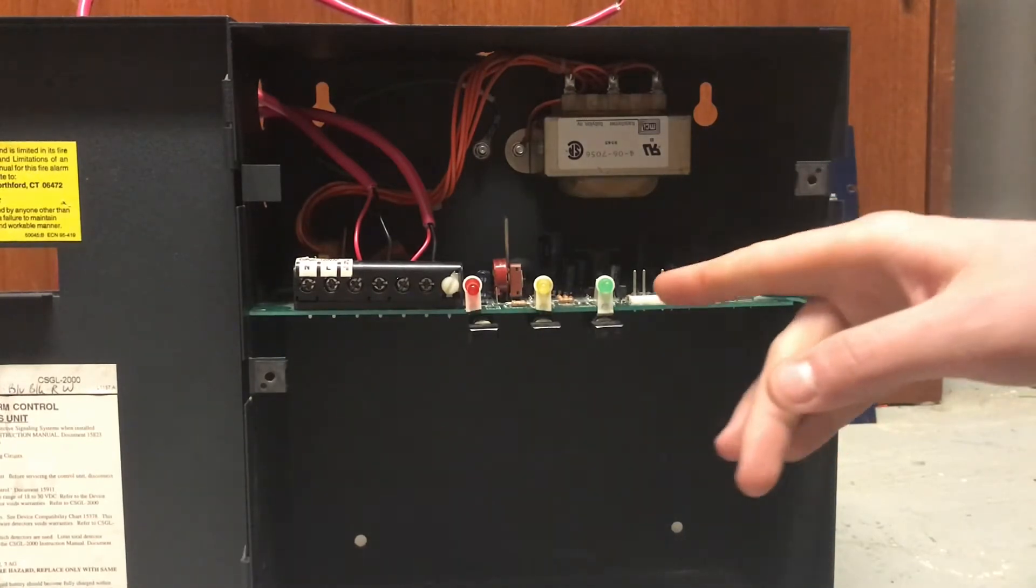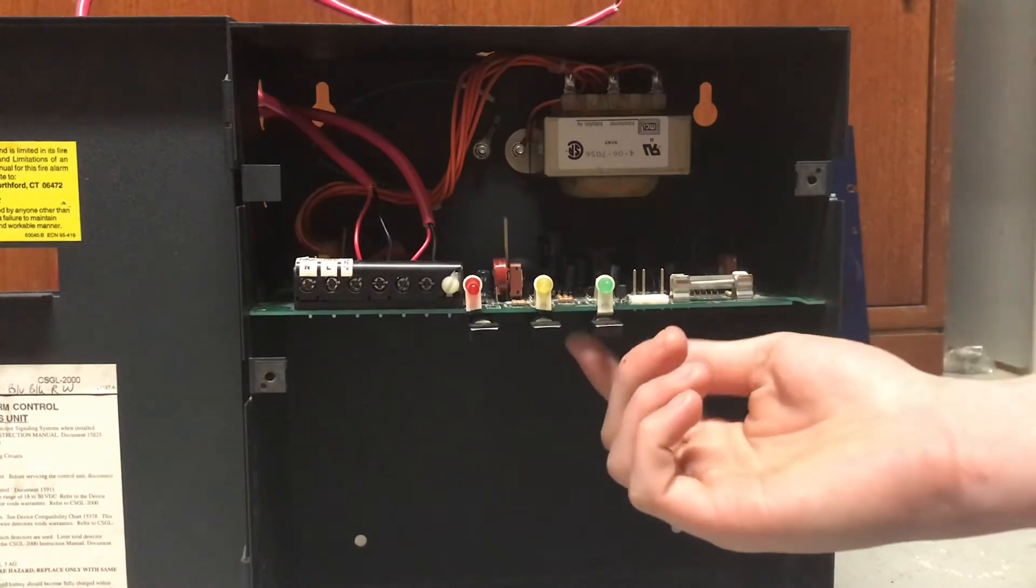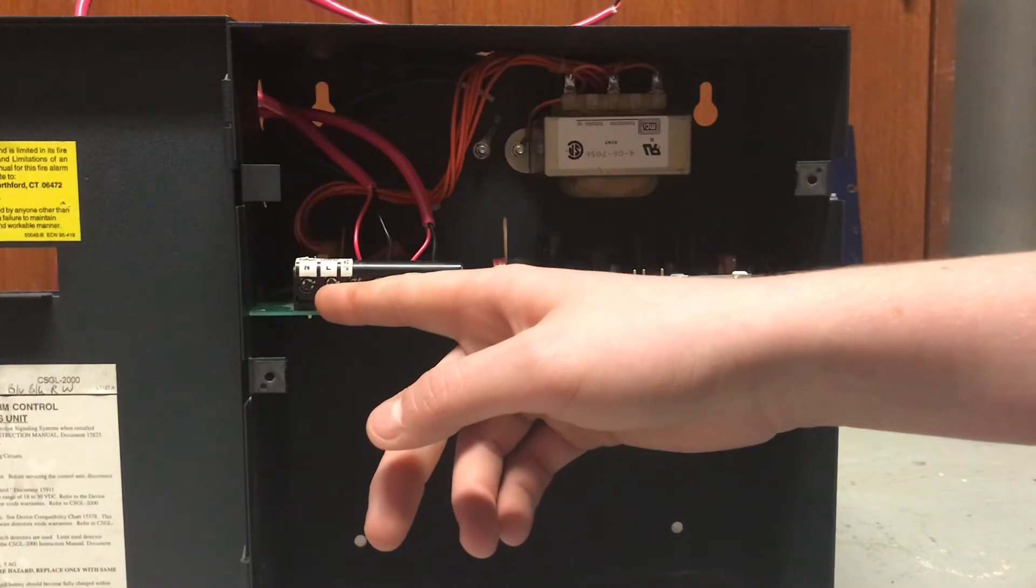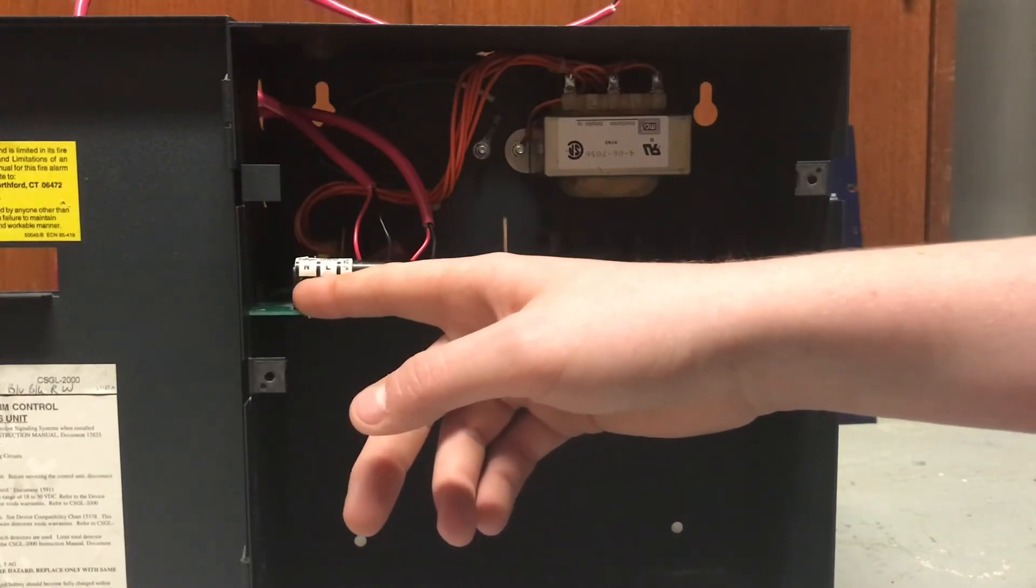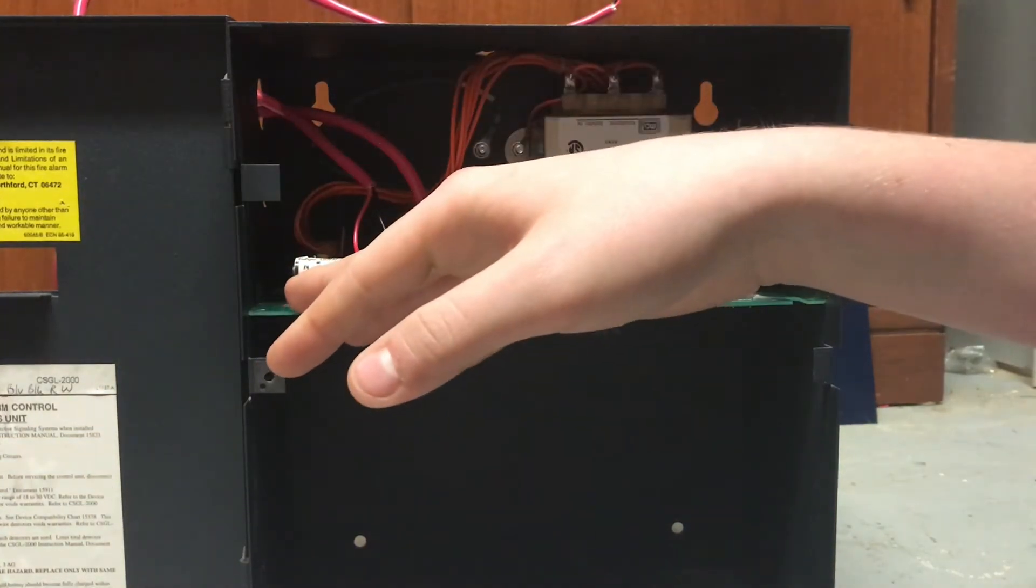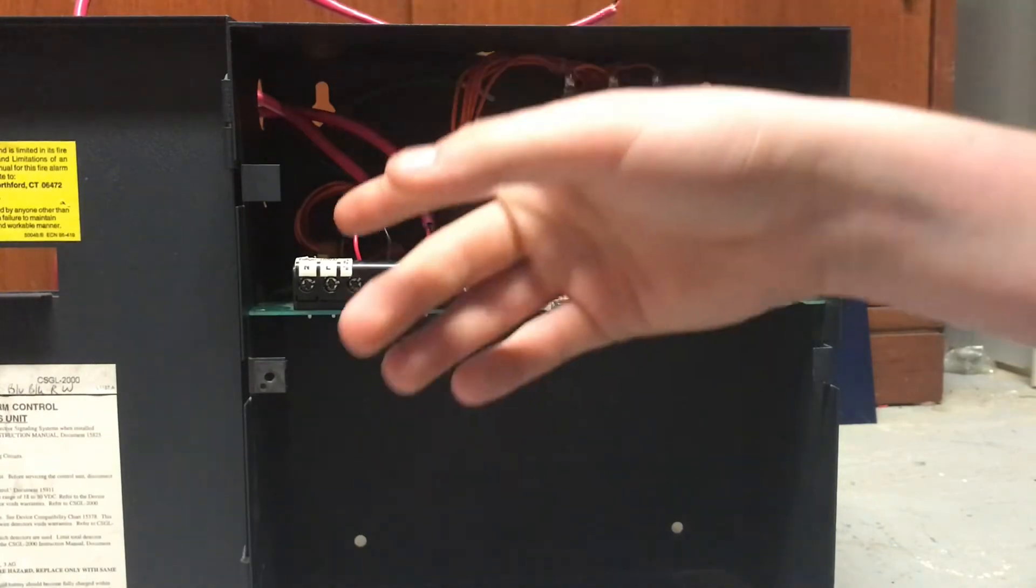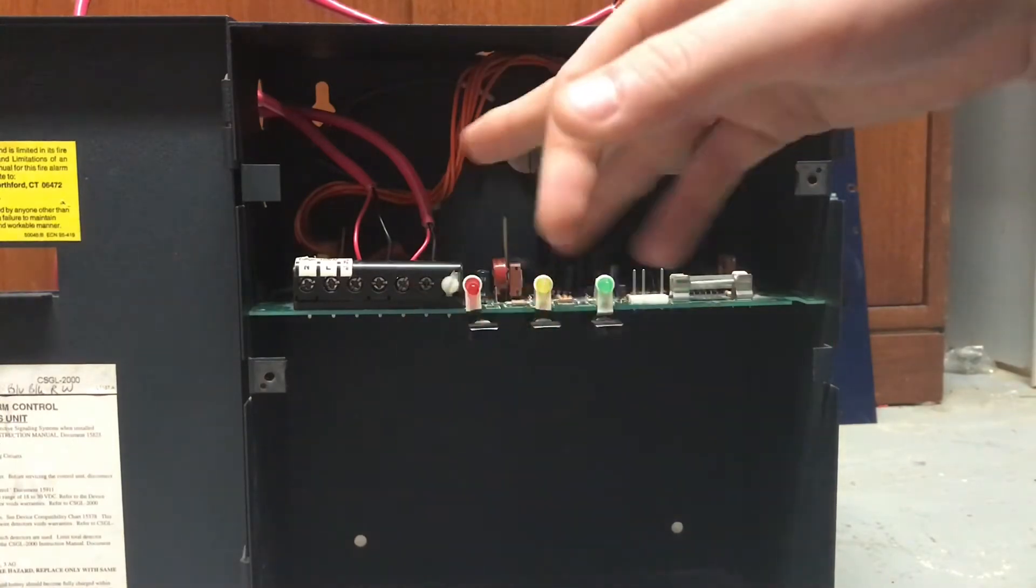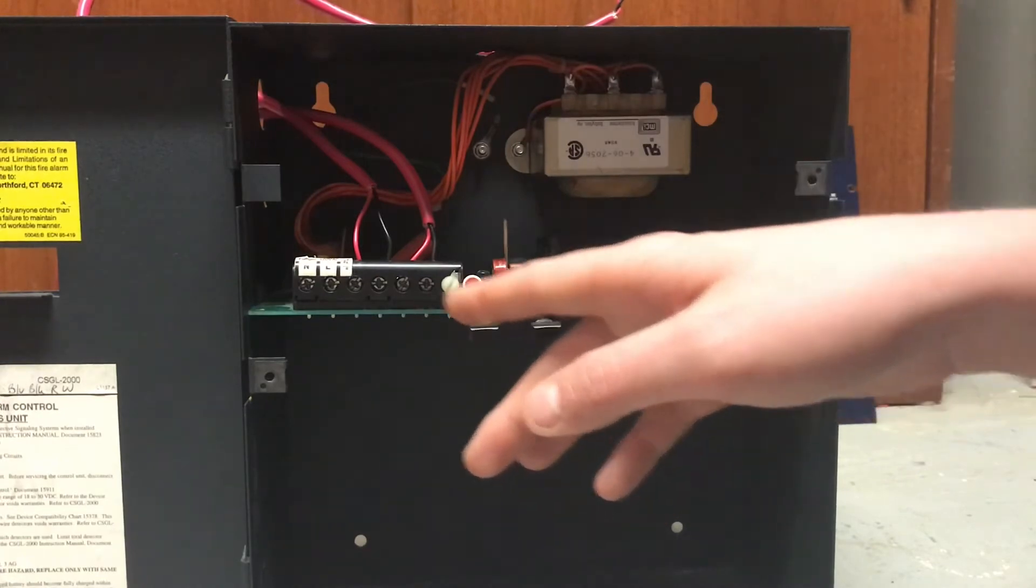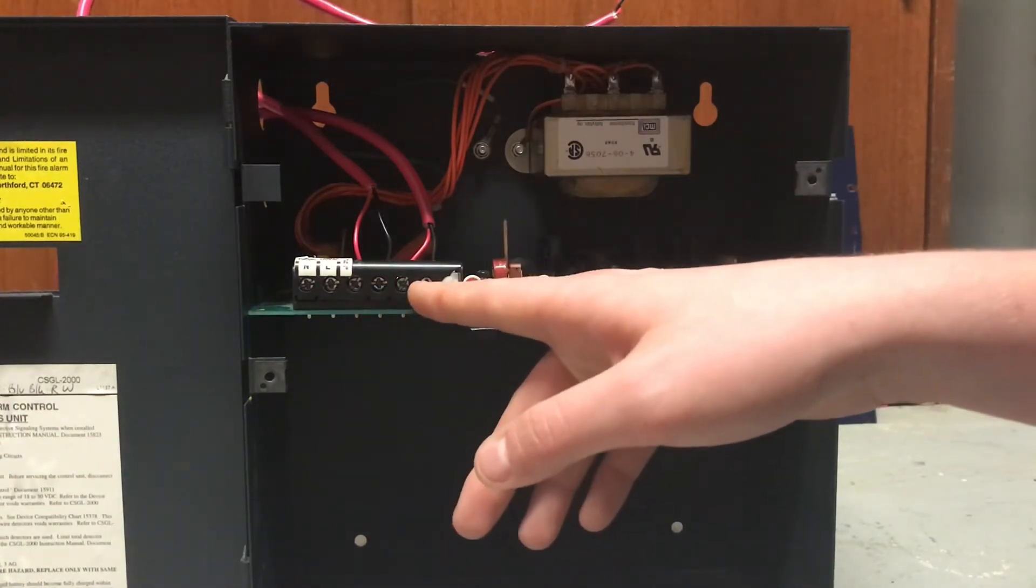Basically here we have your buttons, and they have a spring action underneath. We have your terminals, these two terminals, this is for neutral and high, I believe. But basically your white and black things for your 120 volts AC, and believe it or not, it actually does not have a ground terminal, but you have to ground it separately because there's a ground wire here in the back. Then you have your zone terminals, and then you have your NAC terminals.